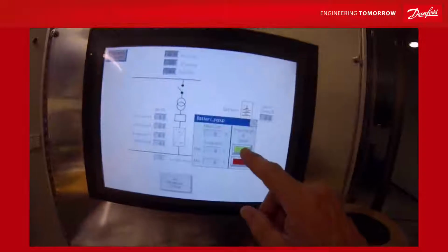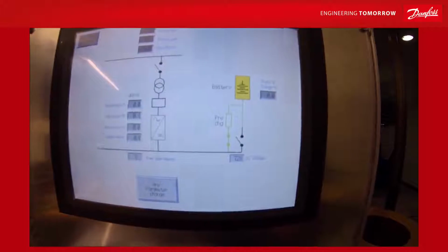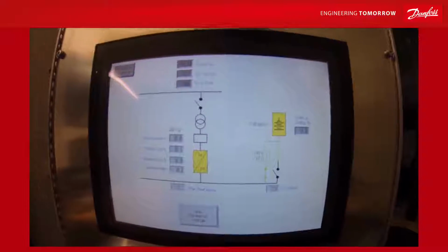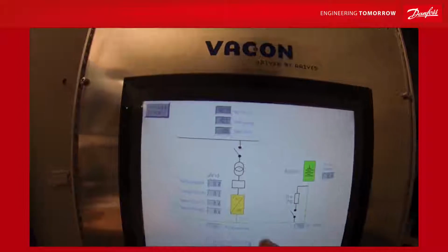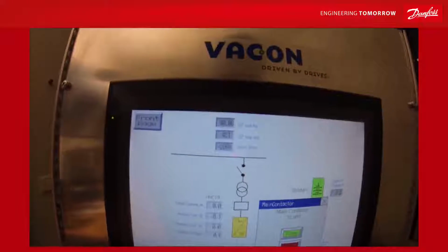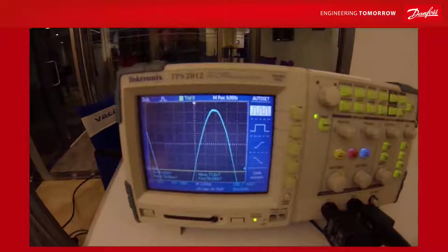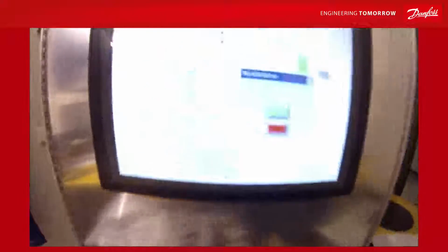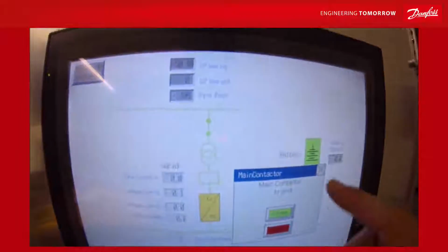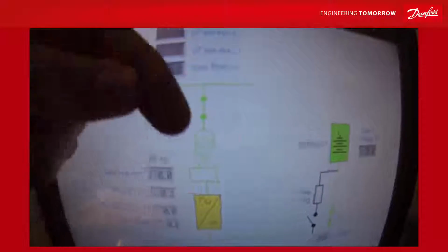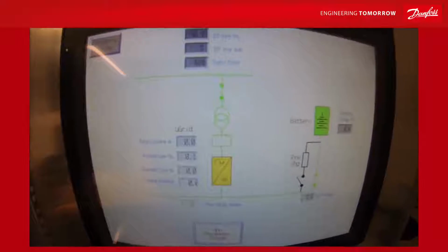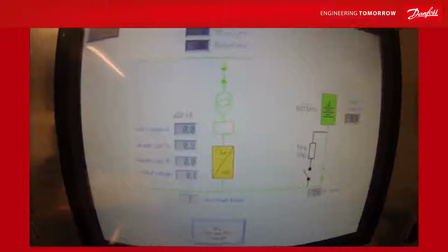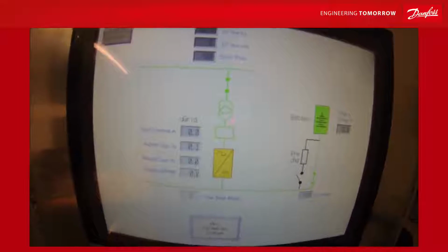First, we pre-charge the drive. And there is two ways of doing this. Now, when the drive is charged, we could just connect it to the grid. I can look here at the oscilloscope. This is the city grid. Okay. If I connect to the grid now, I energize my transformer via the grid. The inrush has to come from the city. They don't always like that, so it's not a very delicate way of doing it.